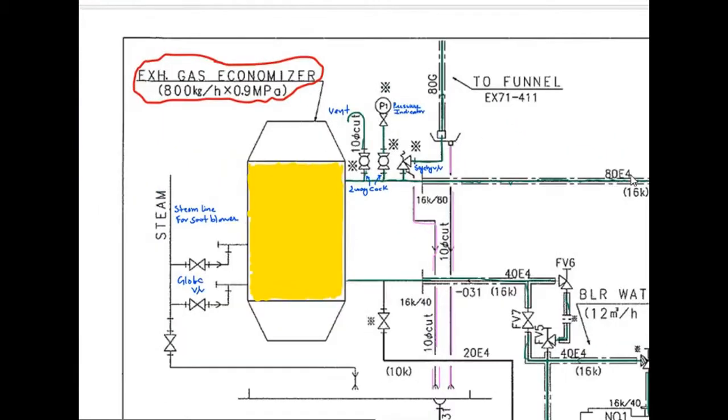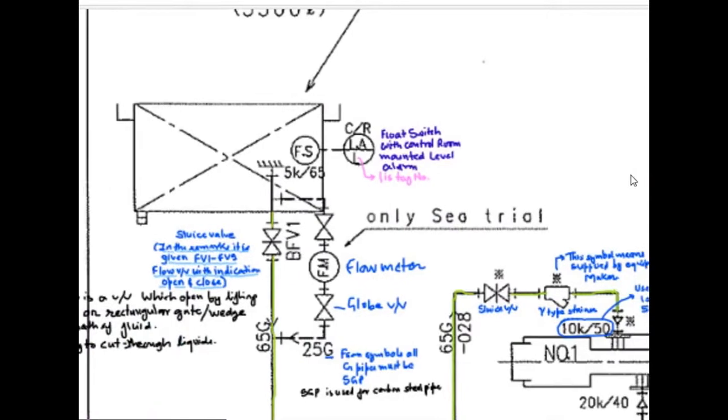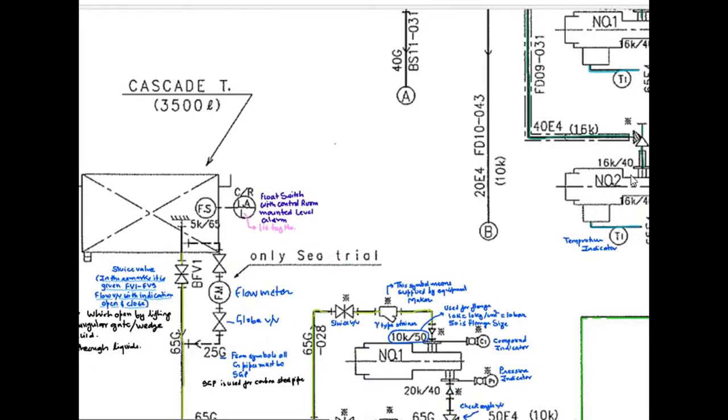At first, we start with Cascade Tank. Here you can see the Cascade Tank is given. Cascade Tank capacity is 3500 liters. Here you can see FS. FS means Float Switch. And this circle and line in between indicates control room mounted level alarm. So it becomes Float Switch with control room mounted level alarm. CR is given for control room. One is given below this line. It means it's a tag number.